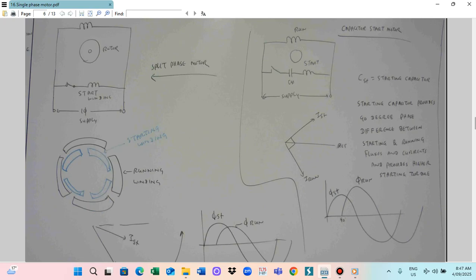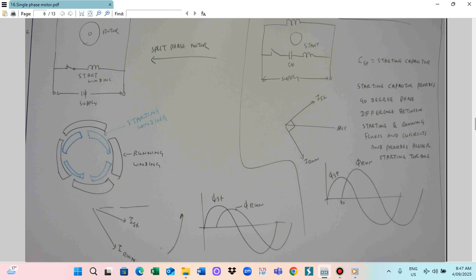So in this case, there will be the running winding here, and then here we use the starting switch, the capacitor, and the starting winding. Then you can connect the supply. So this is the motor, the rotor, and this is the supply.